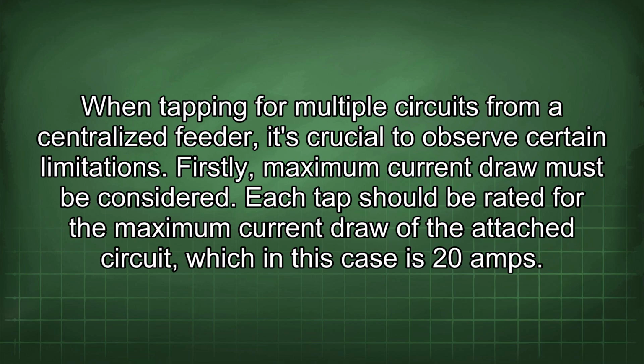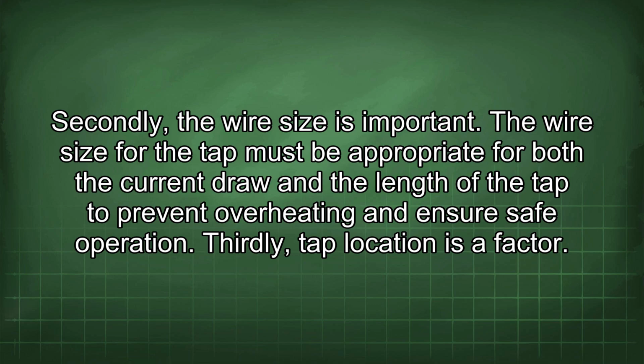When tapping for multiple circuits from a centralized feeder, it's crucial to observe certain limitations. Firstly, maximum current draw must be considered. Each tap should be rated for the maximum current draw of the attached circuit, which in this case is 20 amps. Secondly, the wire size is important. The wire size for the tap must be appropriate for both the current draw and the length of the tap to prevent overheating and ensure safe operation.